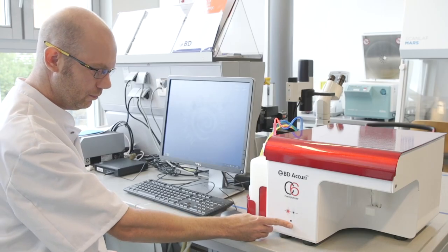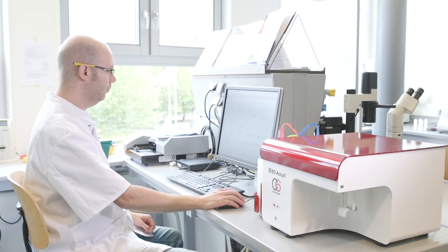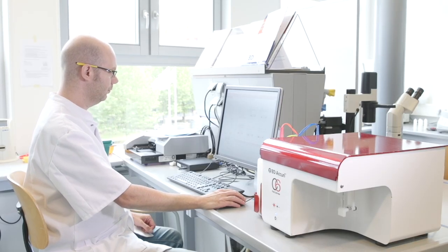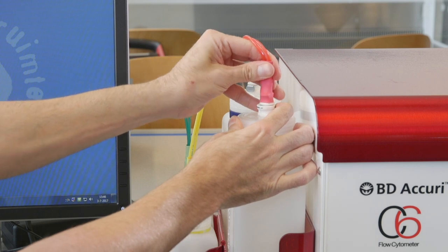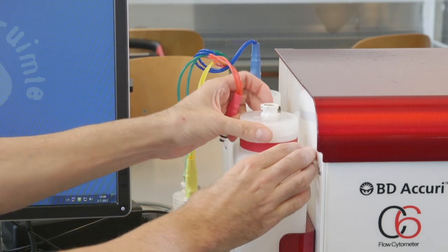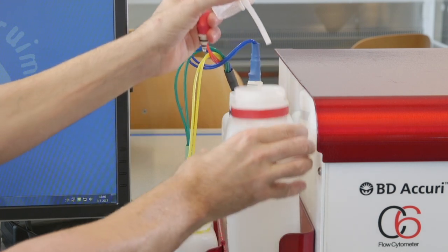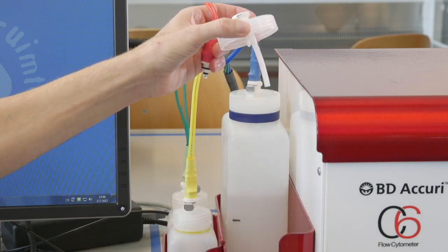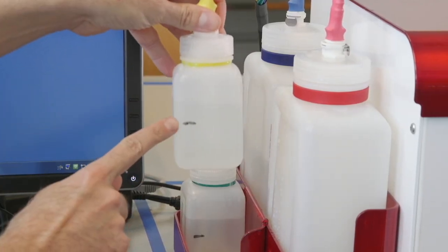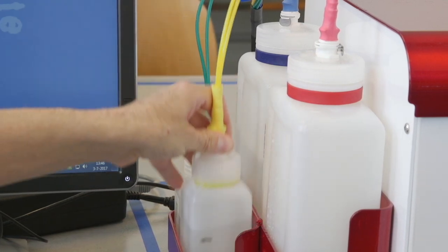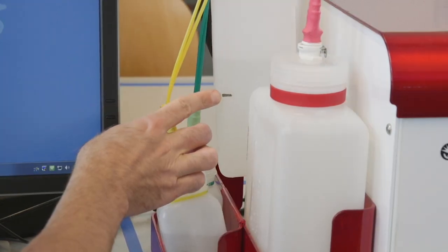Turn on the flow cytometer first and then turn on the computer. Log into the system. Empty the waste bottle before using it. Check the liquid level of the decontamination solution bottle and the sheath fluid bottle.